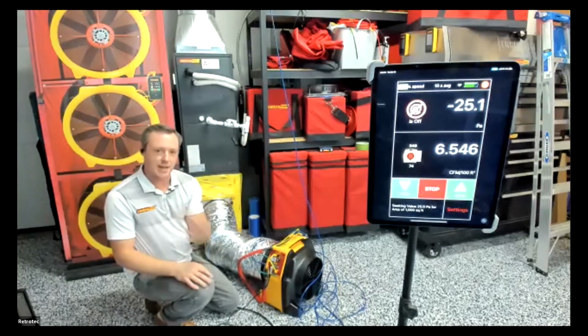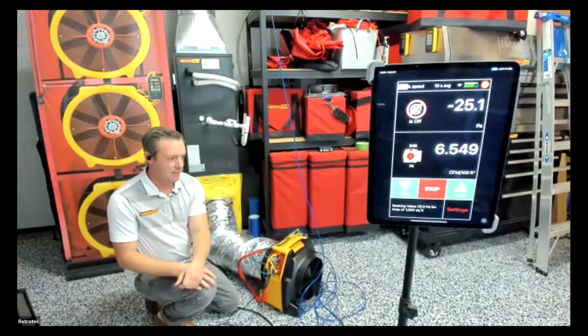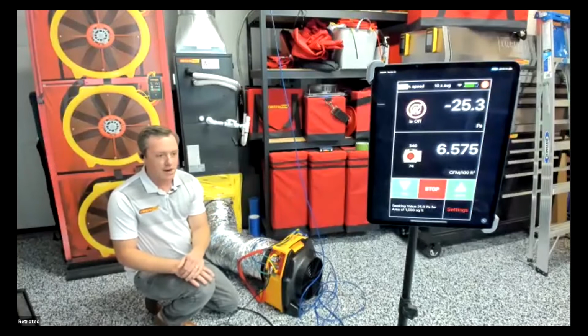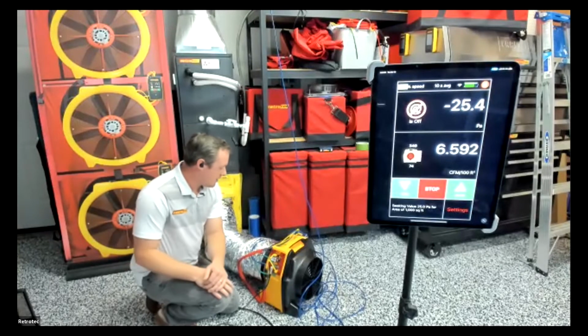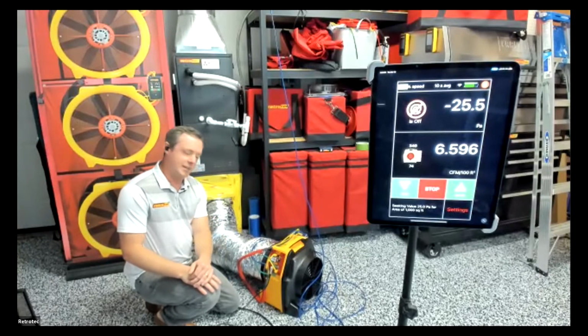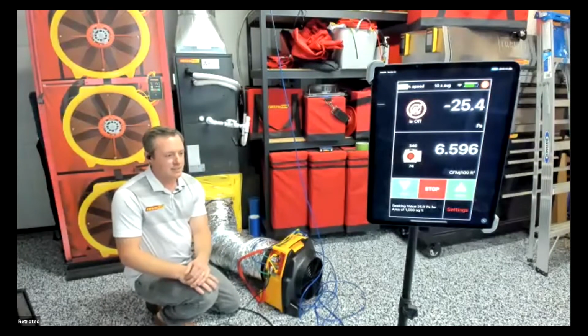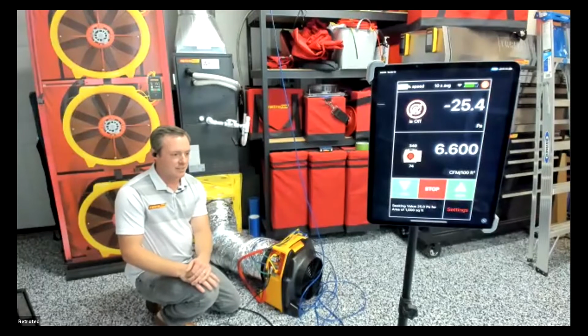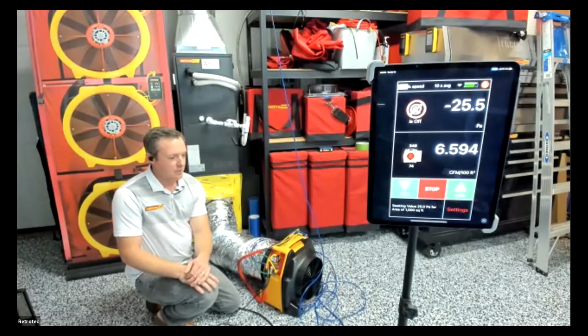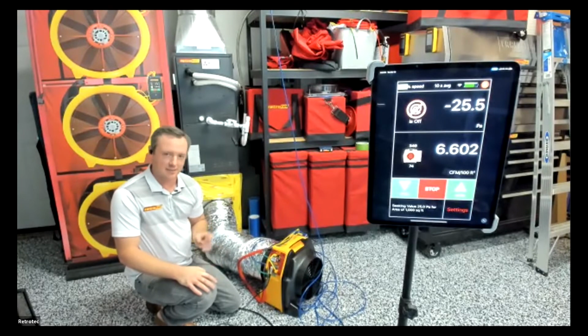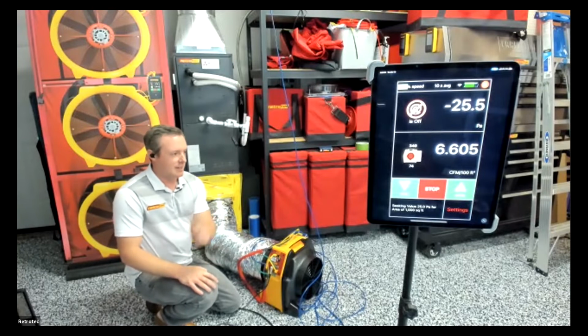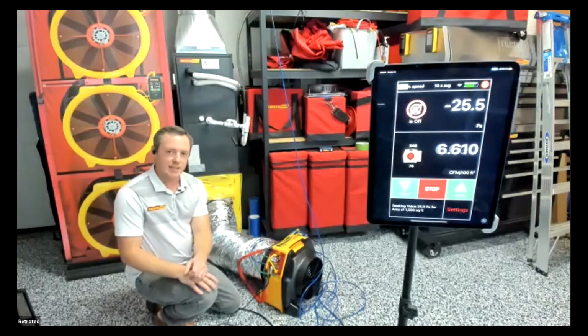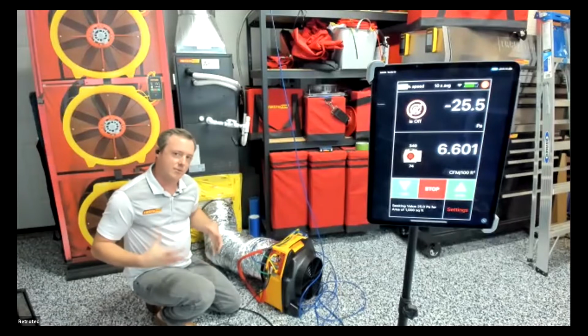That's the one that I used to manage when I was at Advanced Energy in Raleigh, North Carolina. We always required 3% total. And really, to get those tight ducts like that, bucket mastic is the key. John Tooley was the lead building scientist there for years. And one thing he always said was that bucket mastic needs to be as thick as a nickel. And you just want to apply that to every connection that's within the duct system. And that's how you get a really tight number like that.